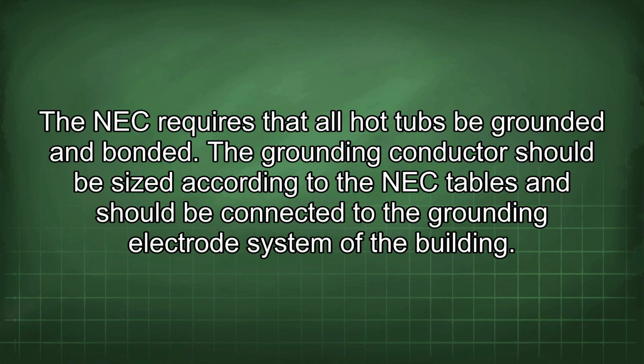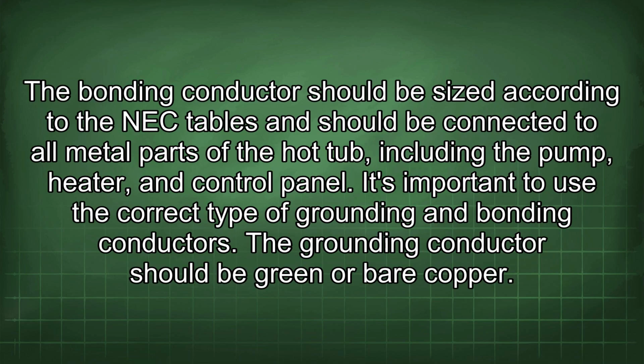The grounding conductor should be sized according to the NEC tables and should be connected to the grounding electrode system of the building. The bonding conductor should be sized according to the NEC tables and should be connected to all metal parts of the hot tub, including the pump, heater, and control panel.